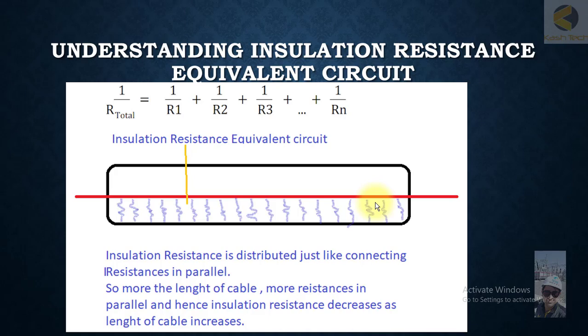If you keep on adding resistance in parallel, the total resistance will keep on decreasing. And that's why the insulation resistance of a cable or any equipment, when you increase the length of the insulation, the value of insulation resistance will keep on decreasing. For example, if you are testing the insulation resistance of a cable of 100 meters...